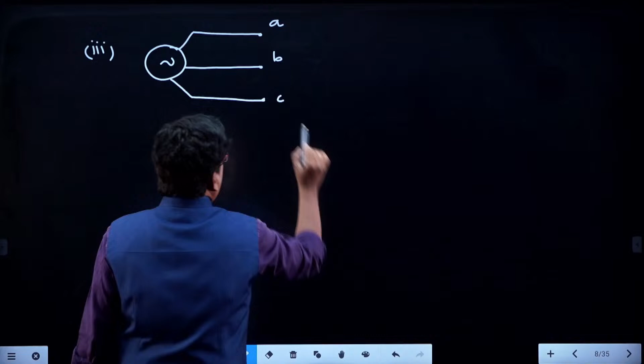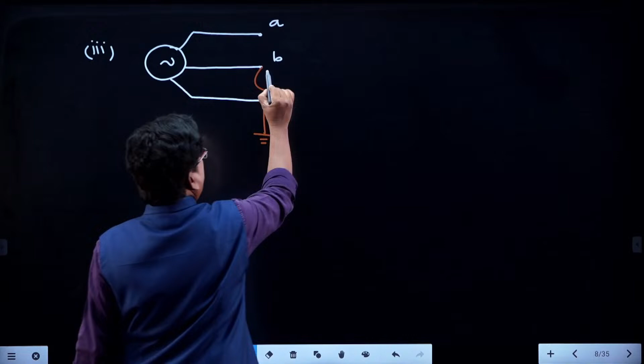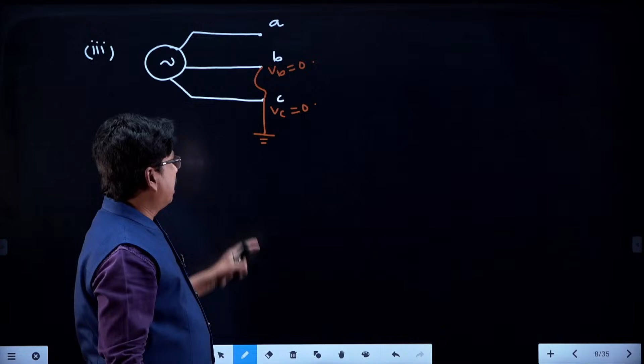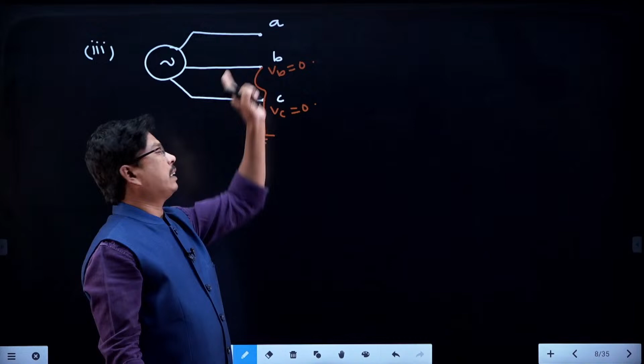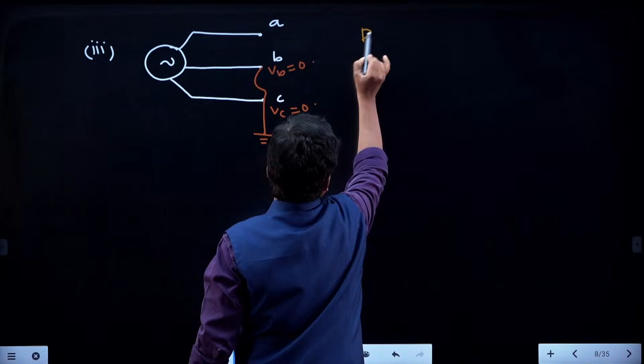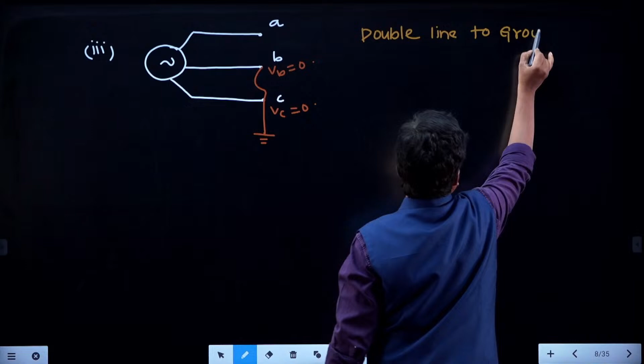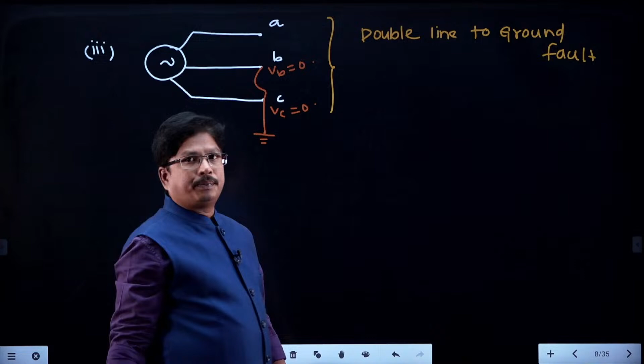Now, if B phase and C phase are short circuited and grounded, under this condition the value of VB is equivalent to 0, and the value of VC is also equivalent to 0. Why? Because the ground potential is going to appear on the lines. Only two phase voltages are 0, the other phase voltage is not 0. It is also an unbalanced fault. This is called a double line to ground fault. Clear, right? So these are the three types of unbalanced faults.